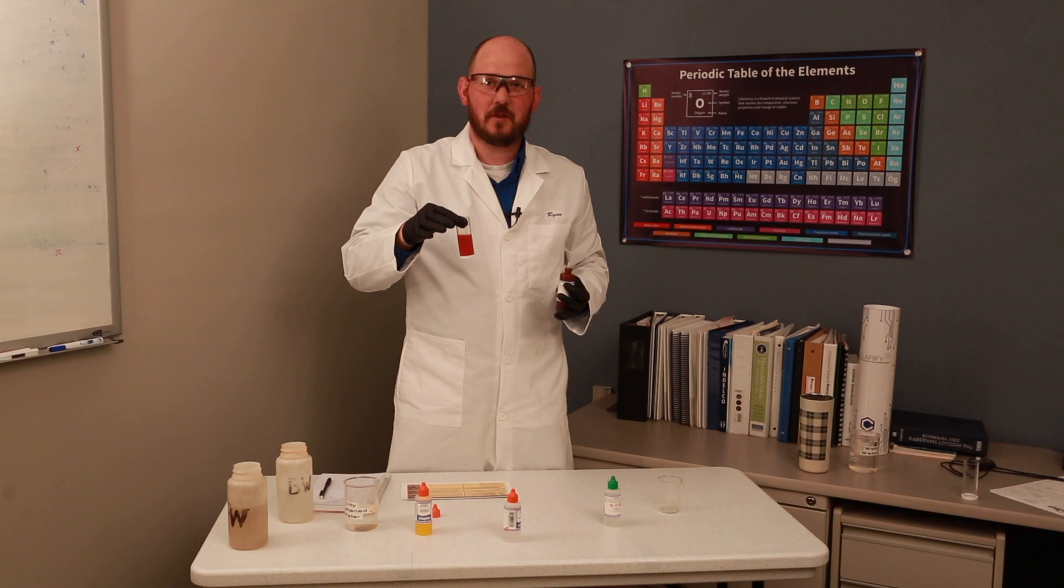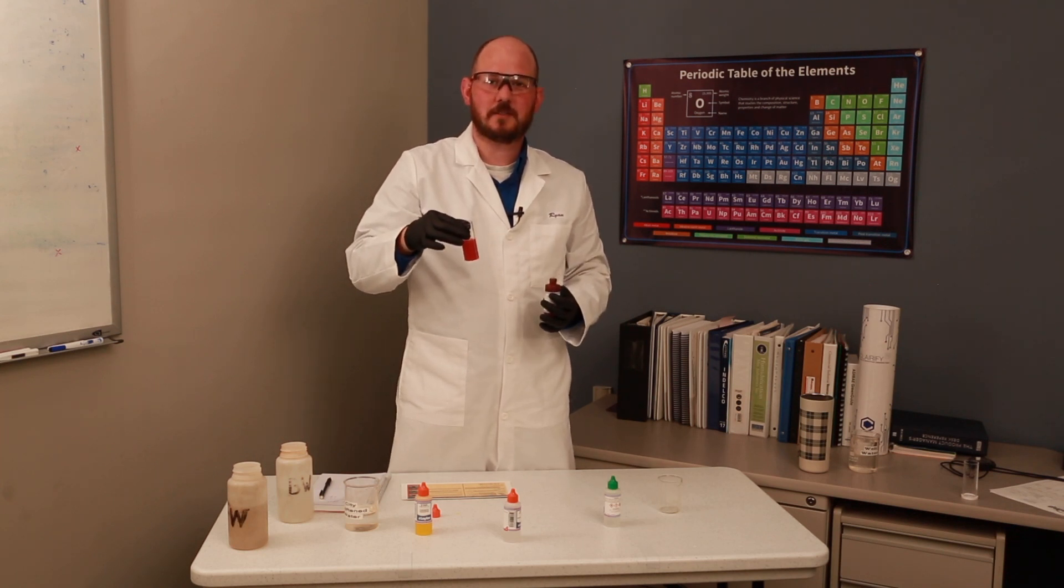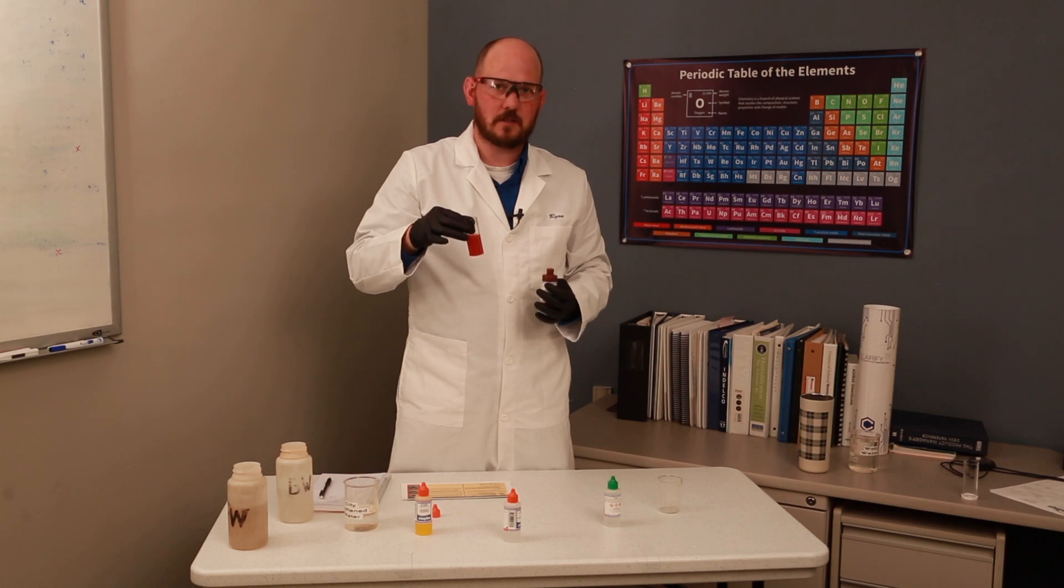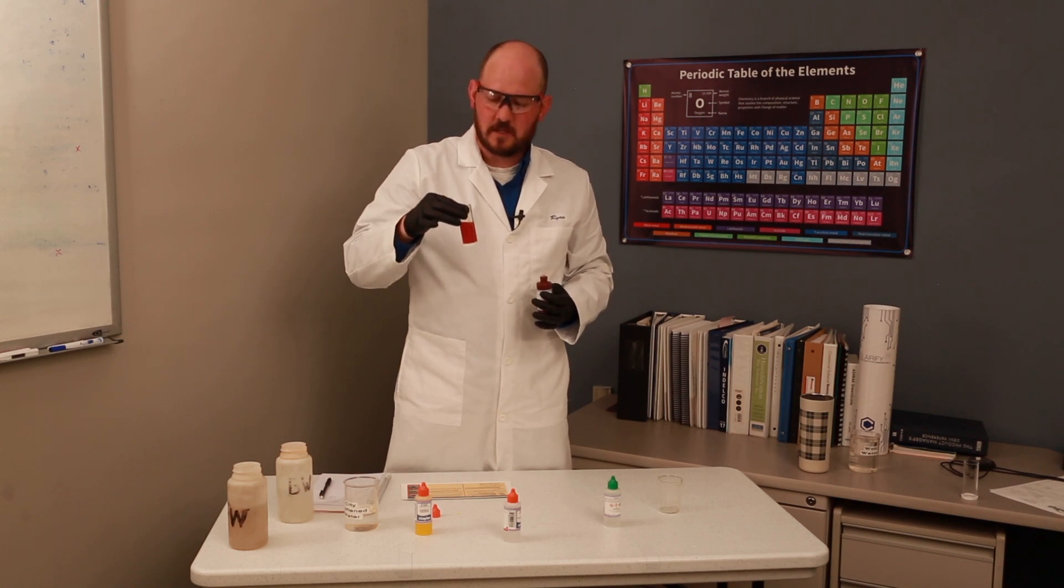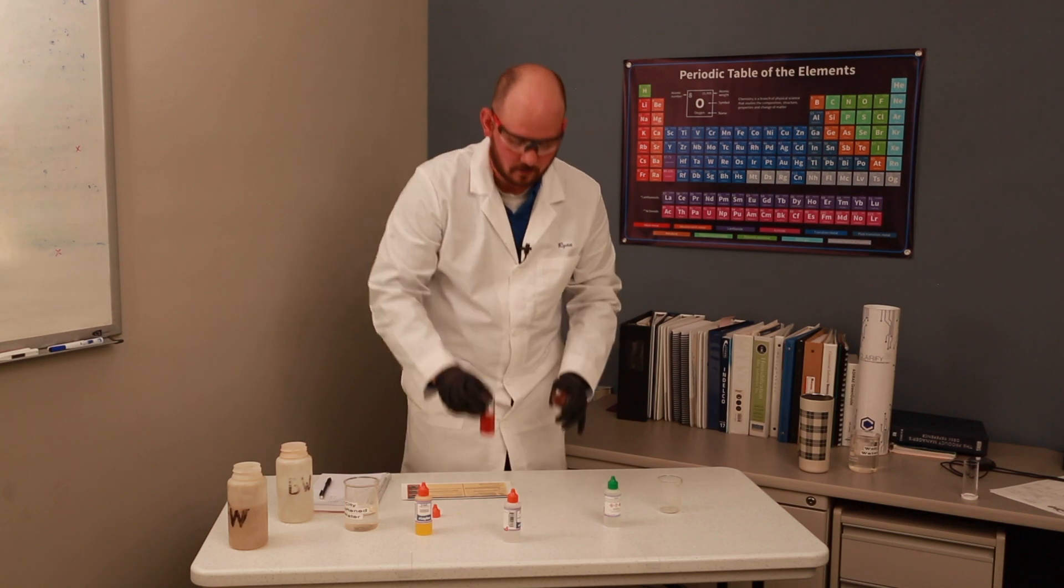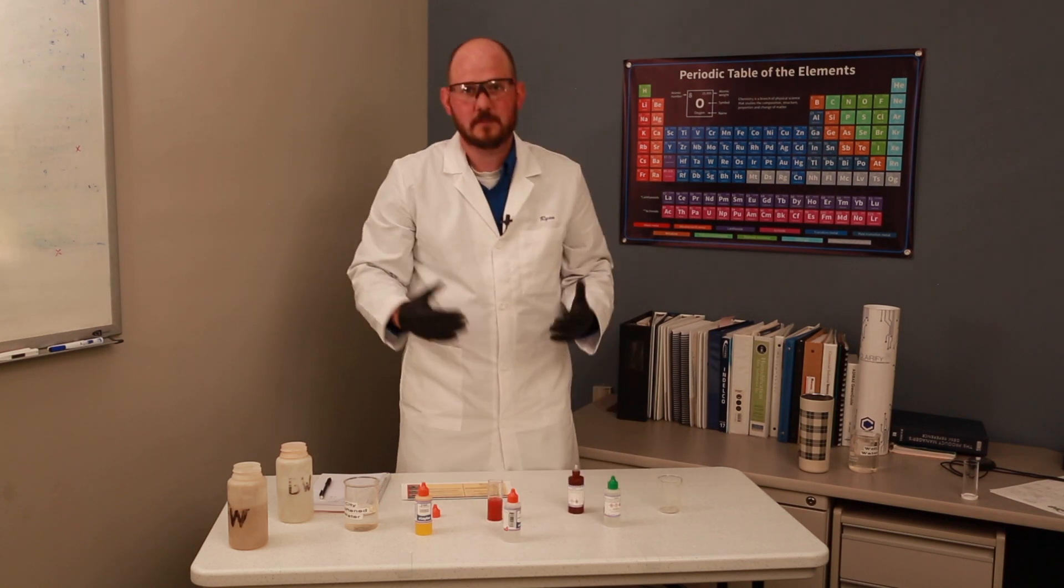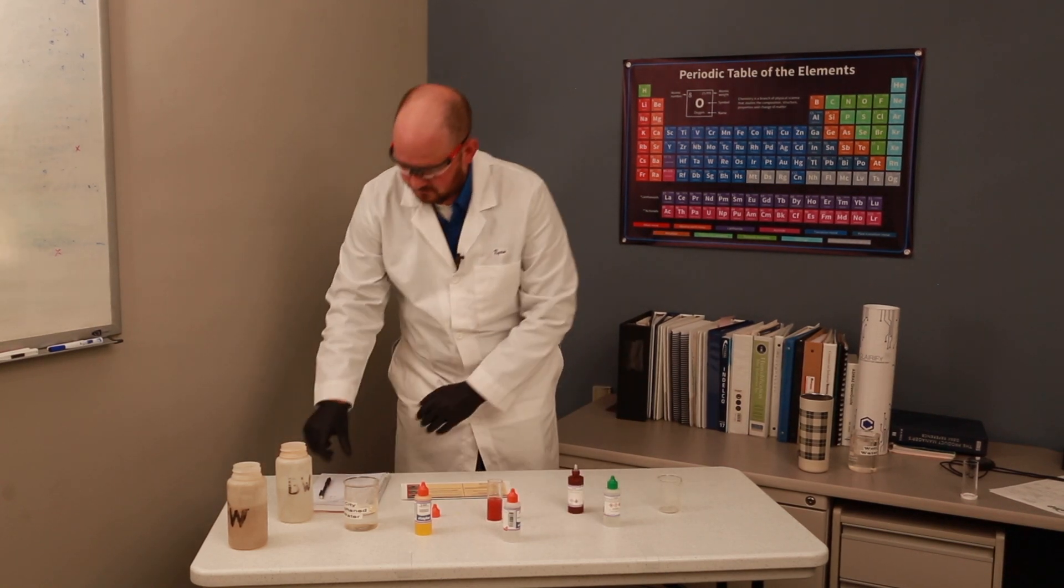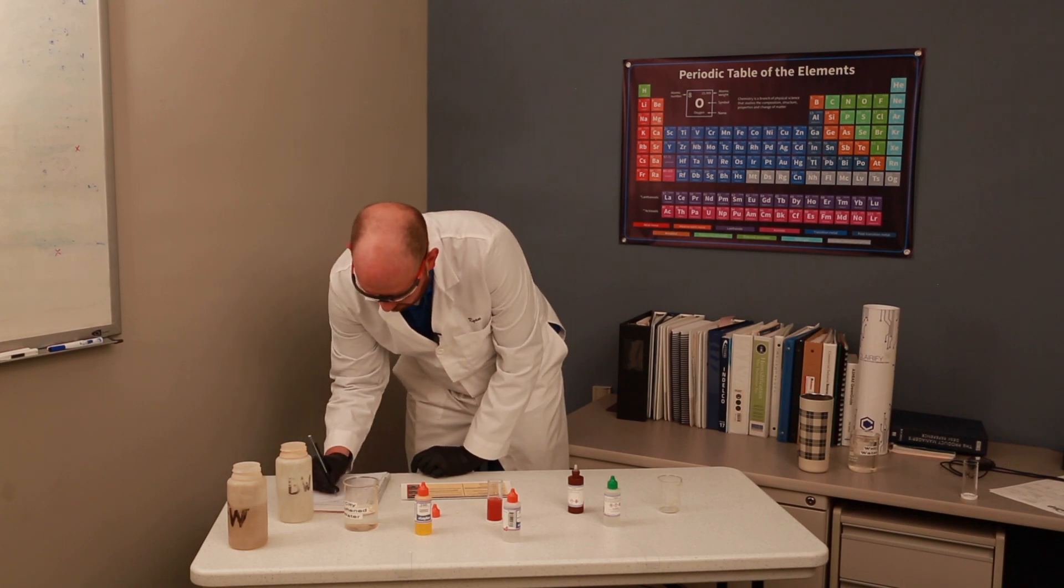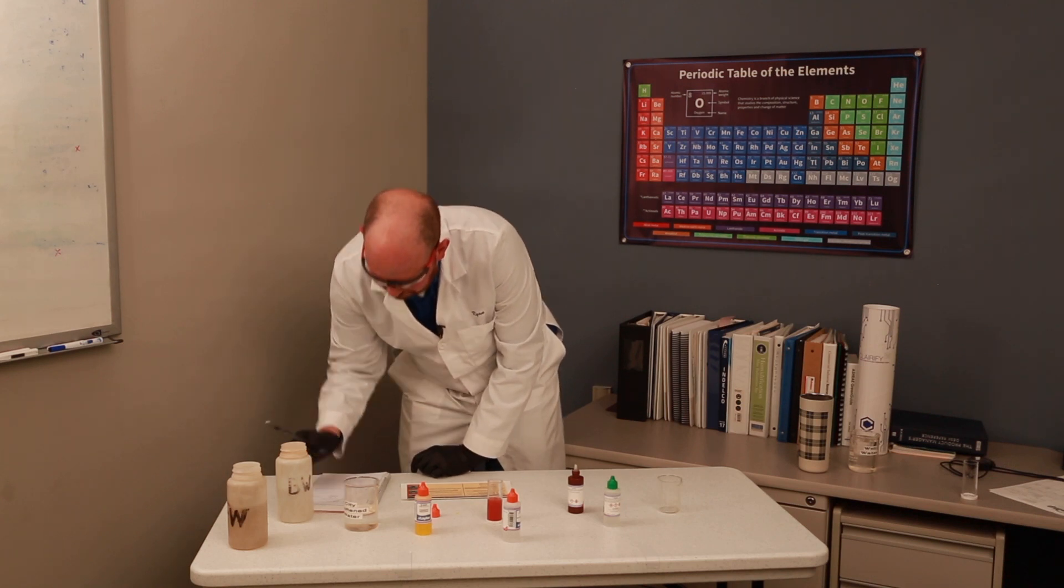The reason this is a different value than the test just a minute ago is this is a different well sample. This is well water versus our softened water supply. So this sample had 70 ppm of chloride - seven drops times 10 gives us 70 ppm. We're going to record that. And with that, this test is concluded.